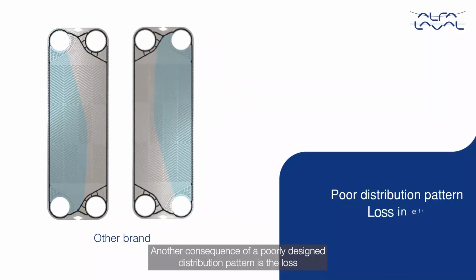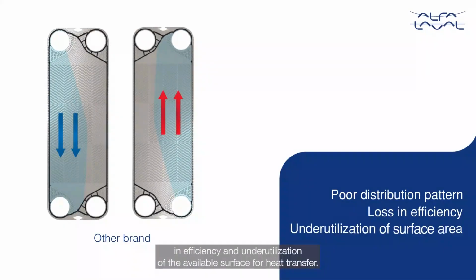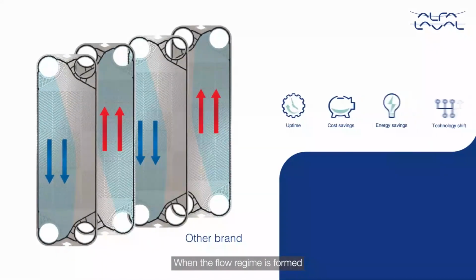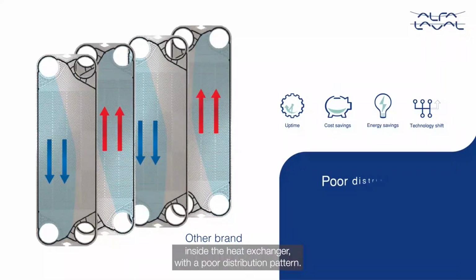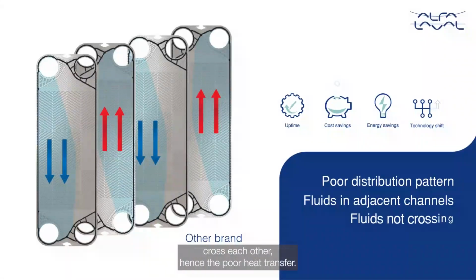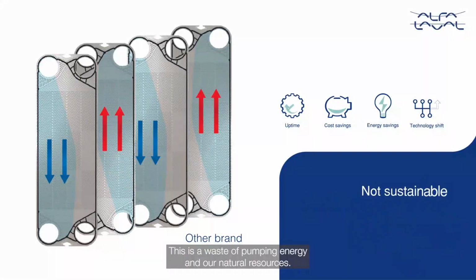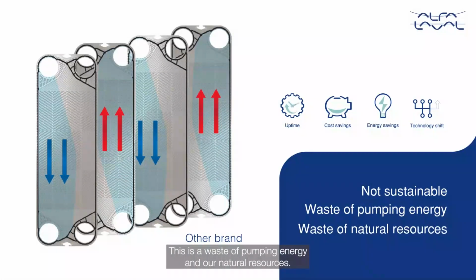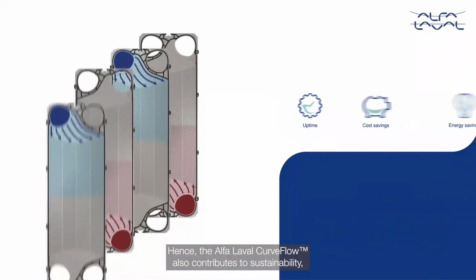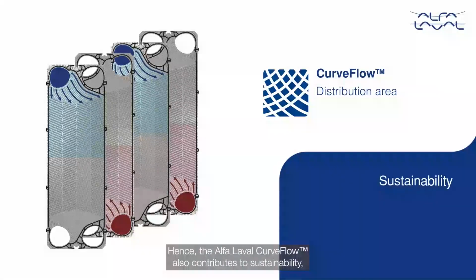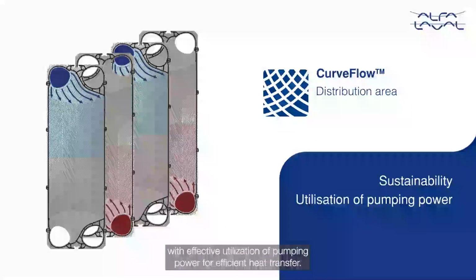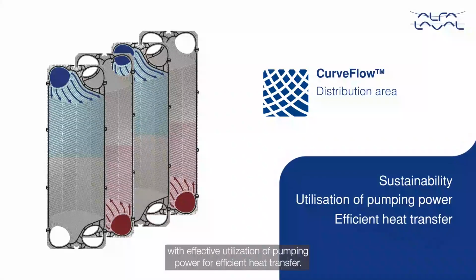Another consequence of a poorly designed distribution pattern is the loss in efficiency and underutilization of the available surface for heat transfer. When the flow regime is formed inside the heat exchanger with a poor distribution pattern, the fluids in the adjacent channels just don't cross each other. Hence, the poor heat transfer. This is waste of pumping energy and our natural resources. Hence, the Alfa Laval CurveFlow also contributes to sustainability with effective utilization of pumping power for efficient heat transfer.